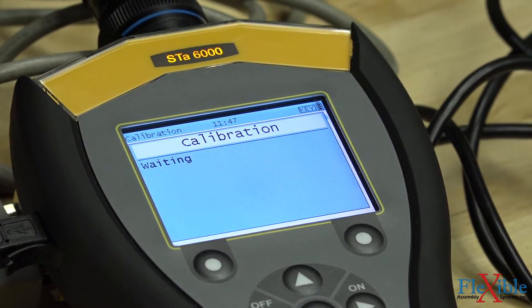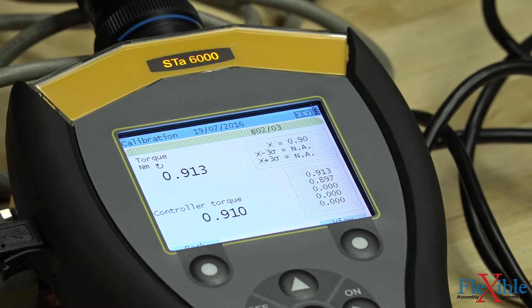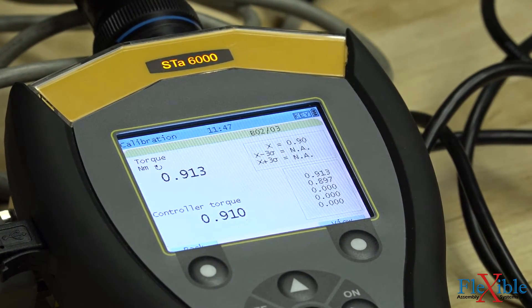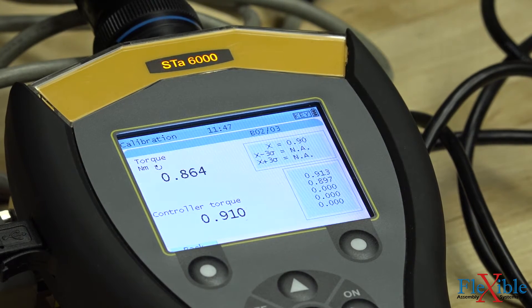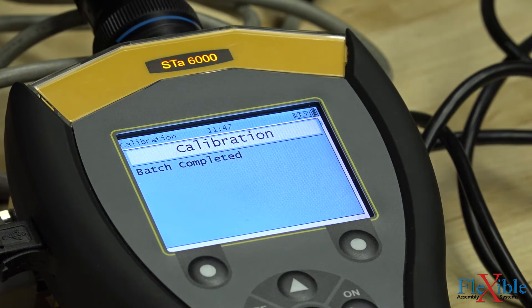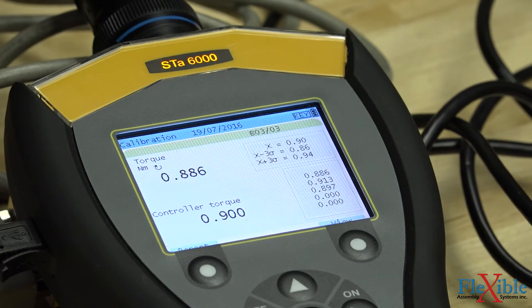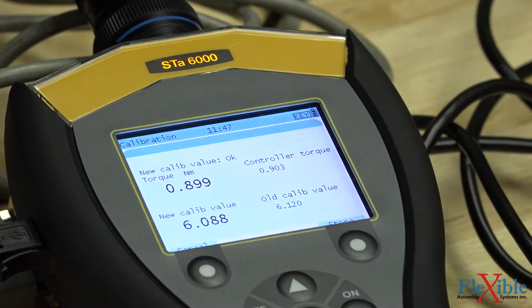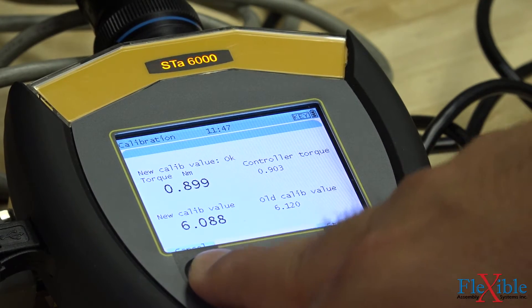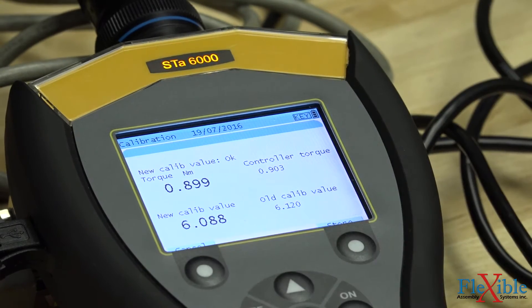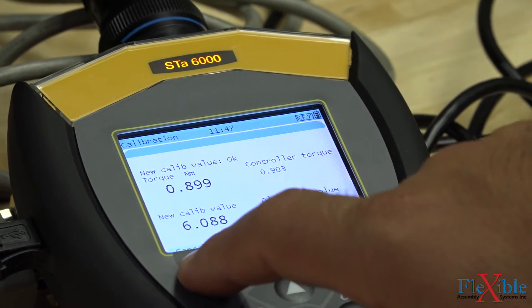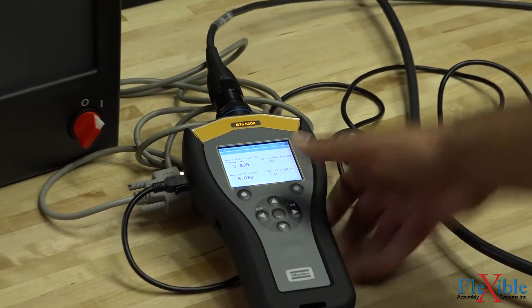Right away, you can see our readings are even closer to each other than before. After the batch is complete, we can now see what the analyzer recommends for our new calibration value. They are so close that they don't need to update it, but we do anyway.